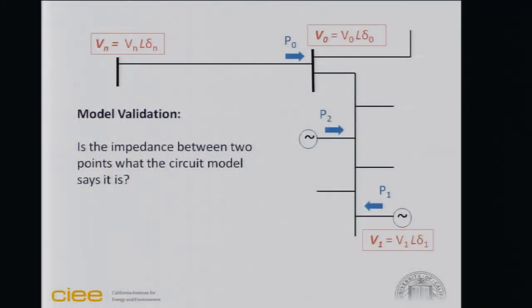The first thing we're working on at LBNL is to validate that the circuit maps, which say what kind of cable there is, agree with the measurements. That's been exciting. We happened to choose a particularly difficult stretch of model to validate. If we had only known that a short section of underground cable that's very lightly loaded and behaves capacitively is really not the easiest place to start with getting all the currents and voltages to make sense together. But we're getting some happy answers.